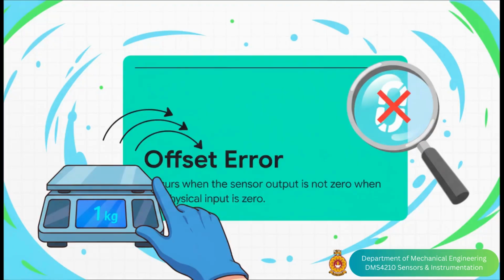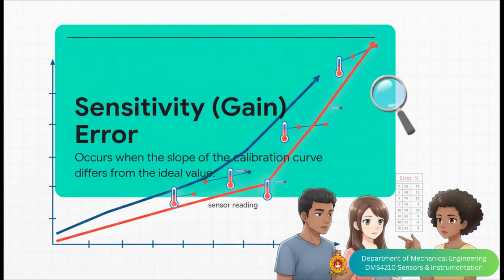So let's break down the common errors this curve can show us. First up is an offset error. The best way to think of this is a scale that says you weigh 1 kilogram before you even step on it. That's an offset. The sensor is consistently off by the exact same amount, no matter what it's measuring. Next, you've got a sensitivity, or gain, error. This one is all about the slope of that line being wrong. So for every 1 degree the temperature actually changes, your sensor might say it's changing by, say, 1.1 degrees. The error actually gets bigger as the measurement gets bigger.